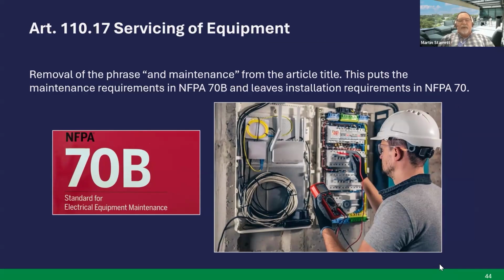110.17, servicing of equipment. They've removed the phrase "and maintenance" from the article title. What this means is this puts the maintenance requirements in NFPA 70B and leaves installation requirements in NFPA 70, which is the National Electrical Code. So now we've got a little split. Installation of electrical equipment is in the National Electrical Code. Maintenance requirements are in the standard for electrical equipment maintenance, 70B. Next slide.